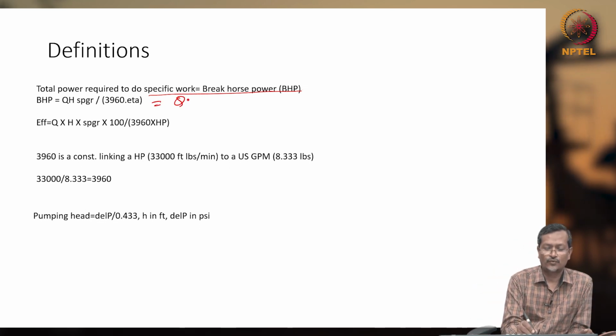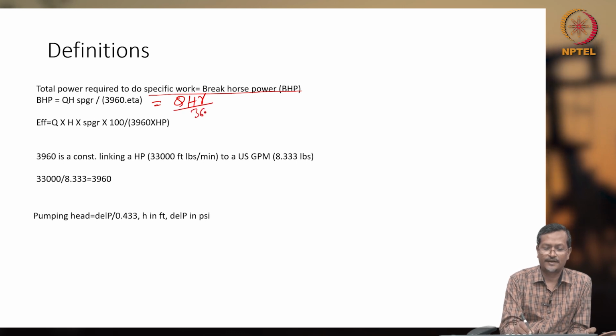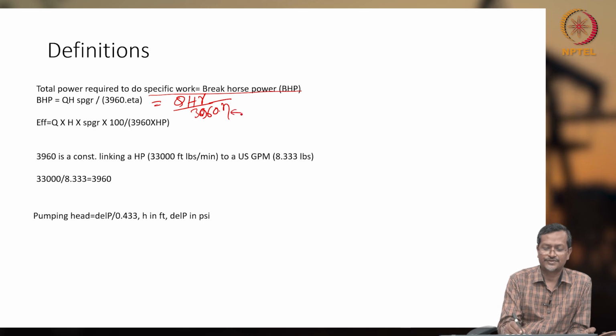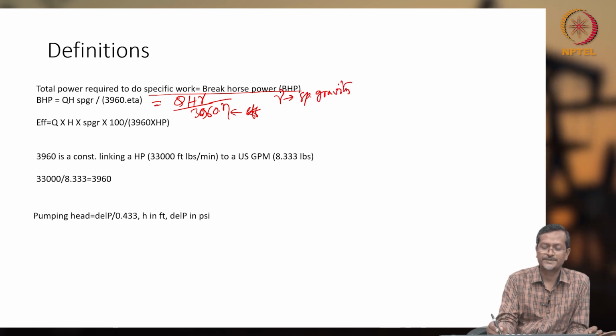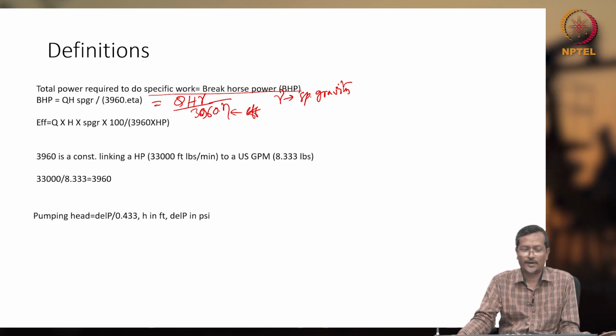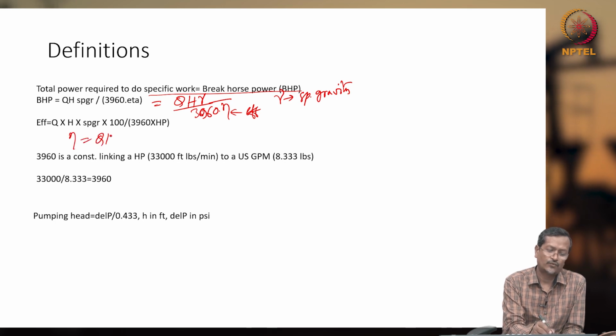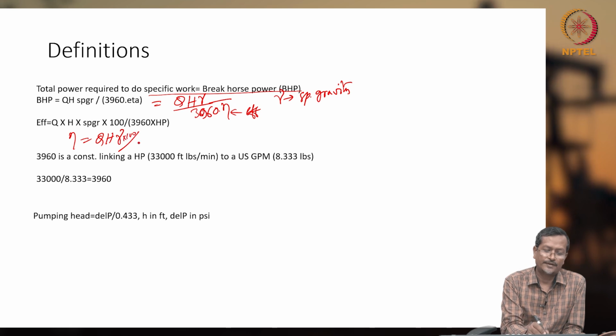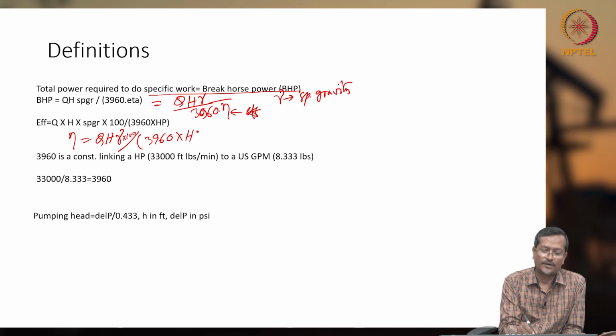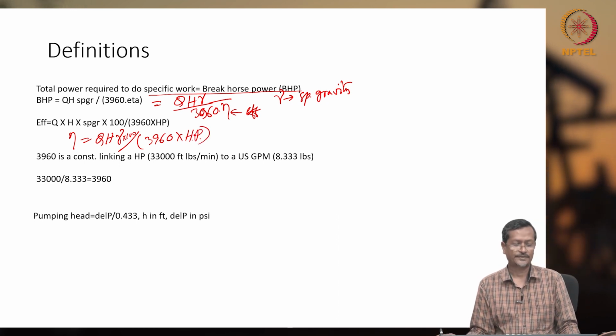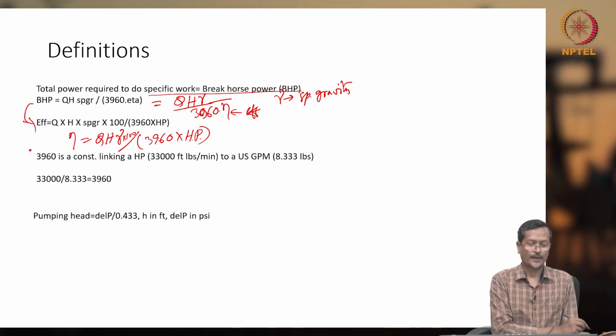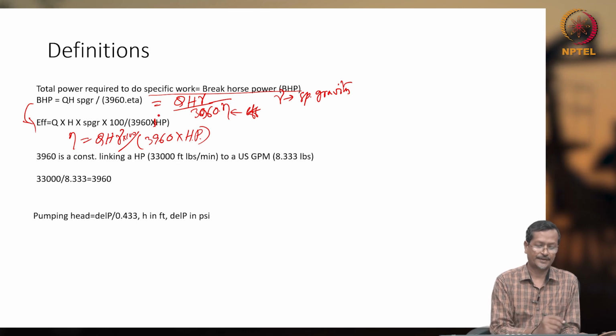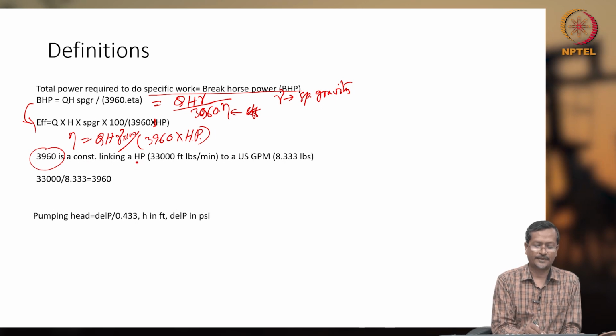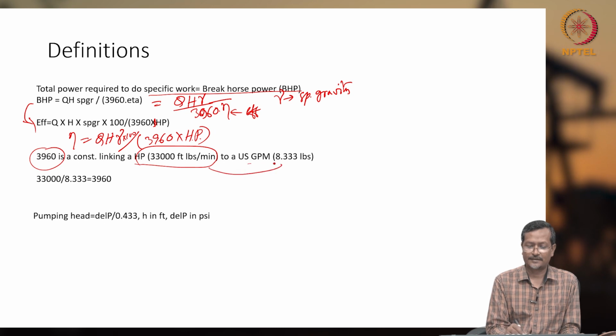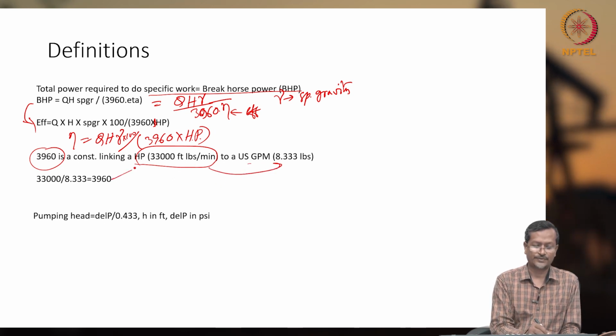Brake horsepower formula is that QH, specific gravity maybe gamma, you can write, over 3960 into eta. Eta is efficiency and gamma is specific gravity. Specific gravity of the fluid you are pumping, that may be water or oil. And the efficiency formula is given, eta equals QH gamma into 100 divided by 3960 into horsepower, okay. How much brake horsepower you have applied, that gives eta. So from this formula actually directly it is coming, okay, or BHP you can write. And 3960, the term is coming from linking HP, feet pound per minute, to US gallon, okay. So minute to second you are doing, and that's why this term is coming, okay.